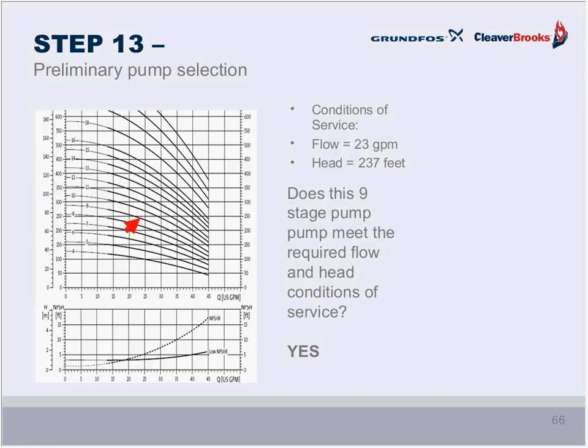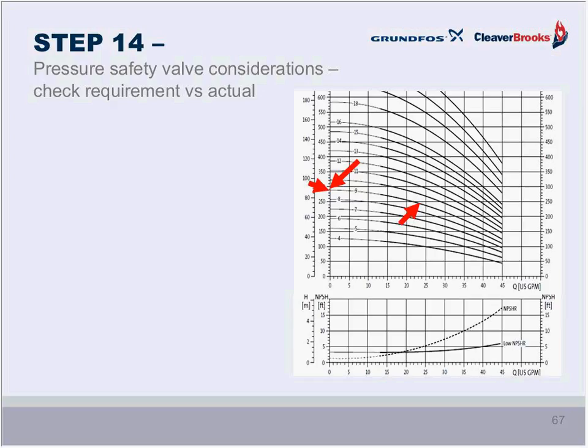Okay. So, yes, we discovered that 9-stage pump can do the job. What about that pressure safety valve consideration? Can we meet the deadhead with this pump? It required 237 feet, or in the middle of the curve, at 23 gallons a minute. But back at 287 feet, what does the pump do? Well, we're okay because the pump can achieve 289 feet. So it's a couple feet higher than the safety valve setting, and that's good. So the pump meets that criteria.